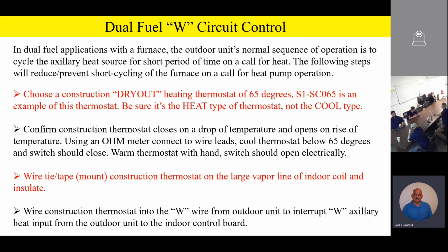Now here's an S1 part number. S1-SC065 is an example of this type of little thermostat. It's just a little thermostat module that you're going to clamp on to the suction line on the indoor coil. And we want to make sure that you select one that's the heating type of thermostat, not the cool type.